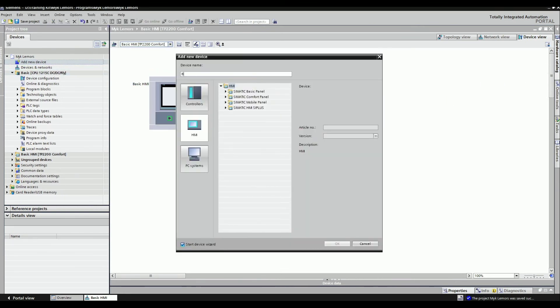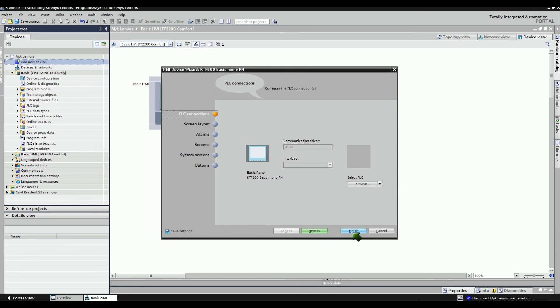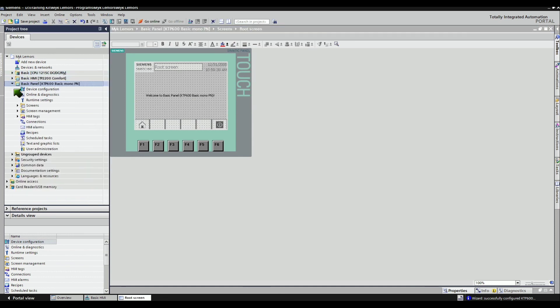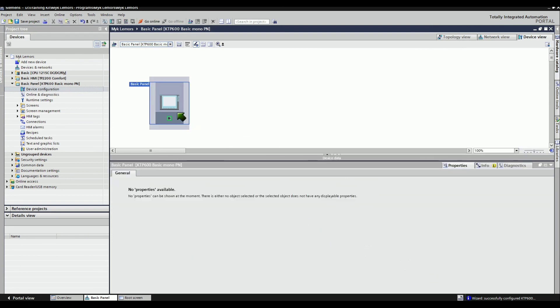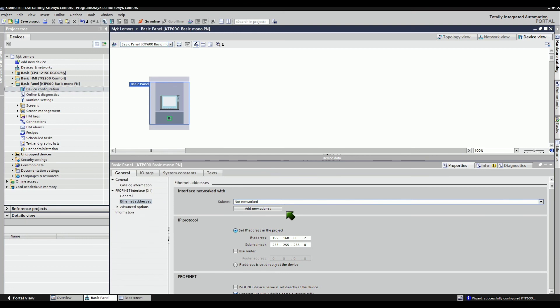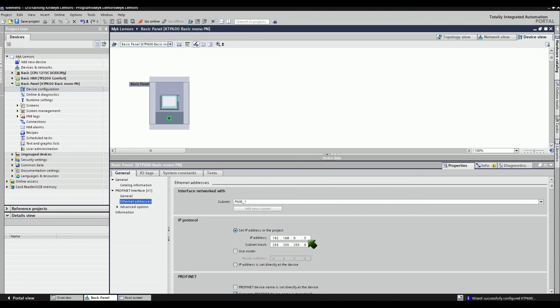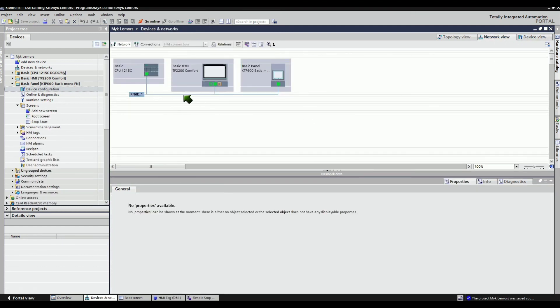Let's add another device. Use the project tree to add a new device. Assign a name for the project, select HMI, and then select the desired HMI panel from the list, and then click OK. This time just leave the default setting, then click the Finish button below. Congratulations! You have created another HMI in the project. Click the HMI in the graphic area and then click Properties. Under the PROFINET interface in the Inspector window, let's add this HMI on the same subnet and set an IP address in the project. Click the Network view — a new subnet is now connected to the PLC and HMI.